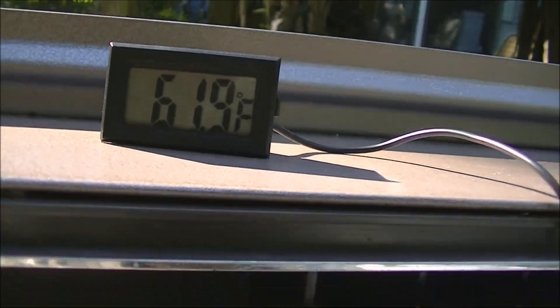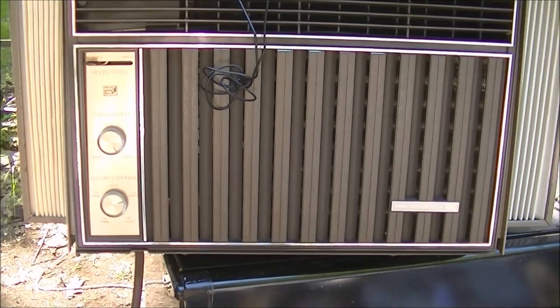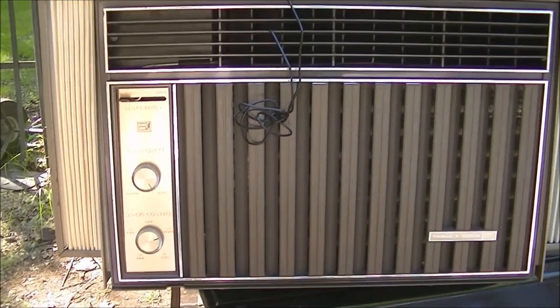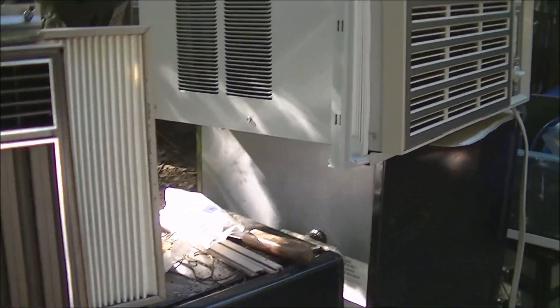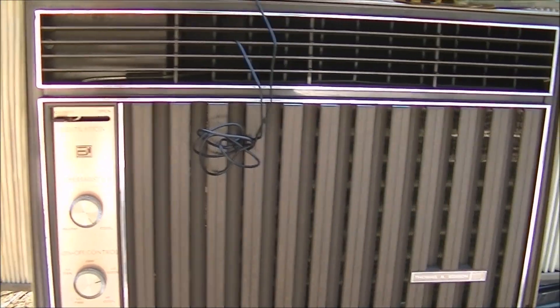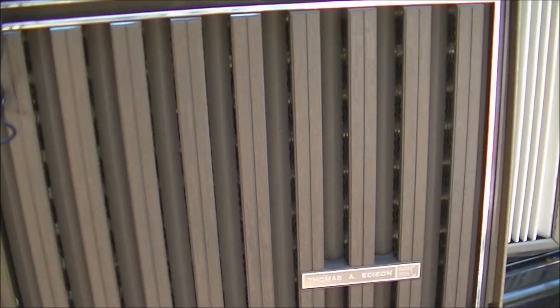I've had this running for a while - just doing a temperature check on it. This is reading 61.9 - 62 degrees. It's about 84 degrees here and it's real humid, so it's probably about right. I turned on that Amana and that reads about 58. So it's probably about right - that's a bigger air conditioner. 58.6 degrees - that's probably about right.